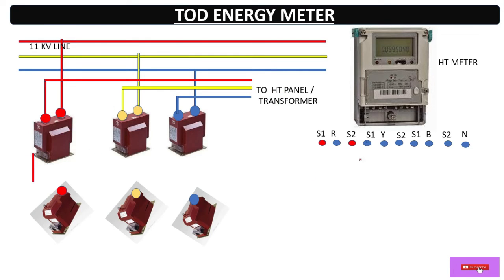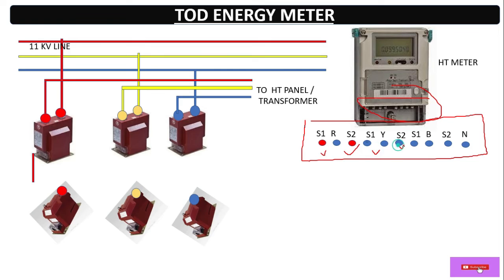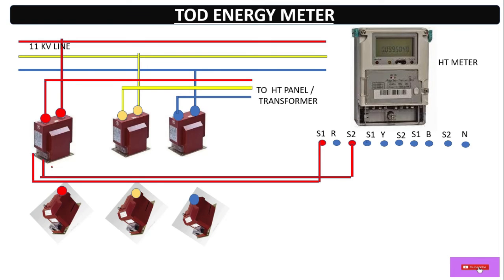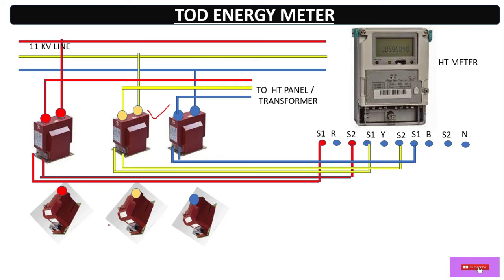Now for the CT secondary wiring, we have terminals S1 and S2 for each phase. For R phase: S1 connected, then S2. For Y phase CT: Y-S1, then Y-S2. Similarly for B phase: B-S1, then B-S2. This completes the CT secondary wiring. For all three phases, we loop the S2 terminals together and earth them — making it a common earth point.